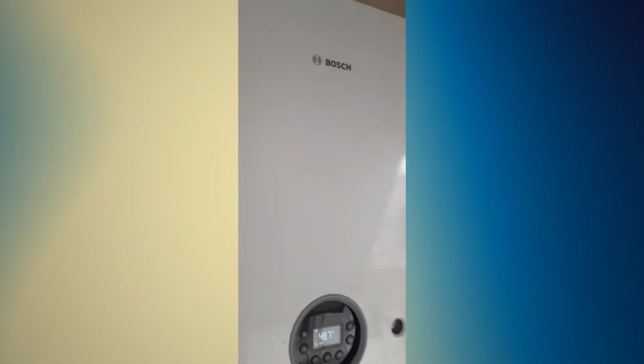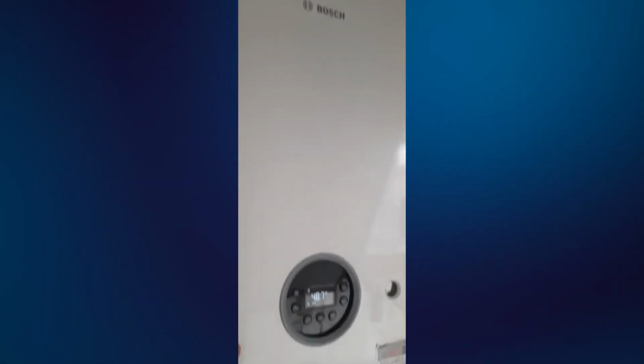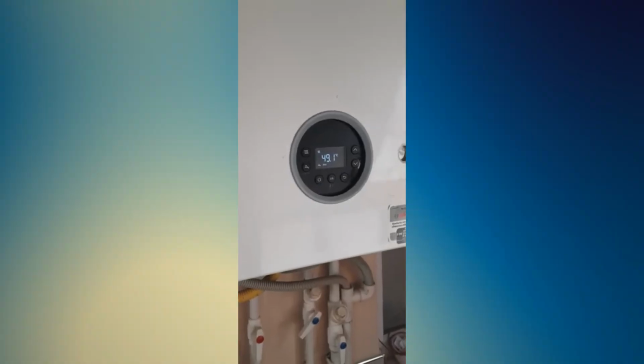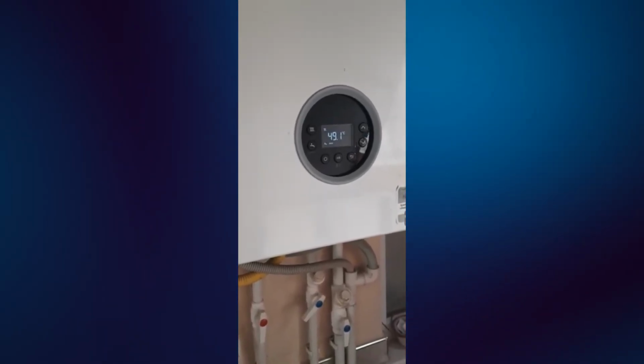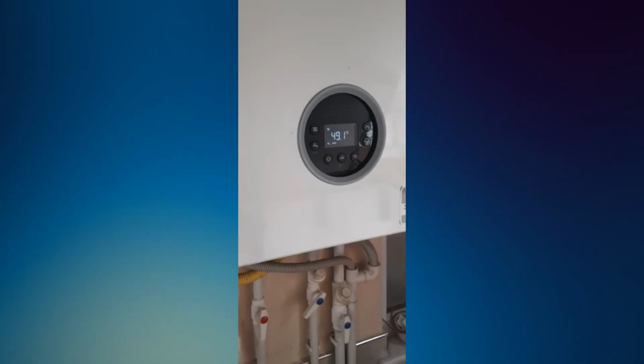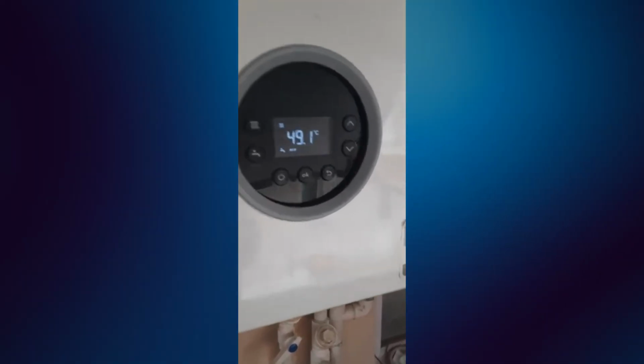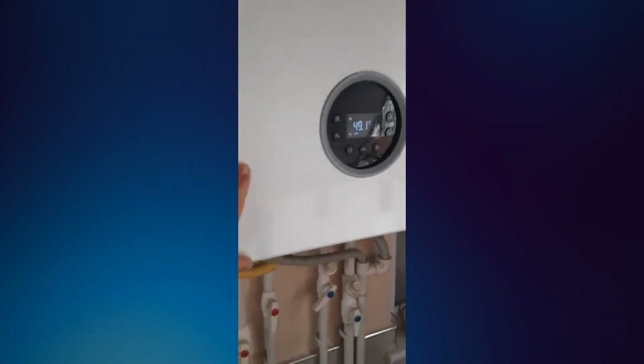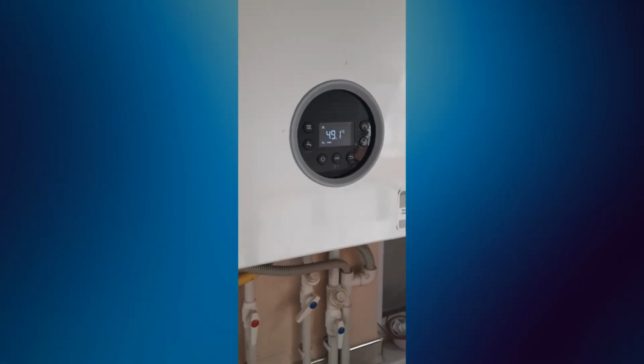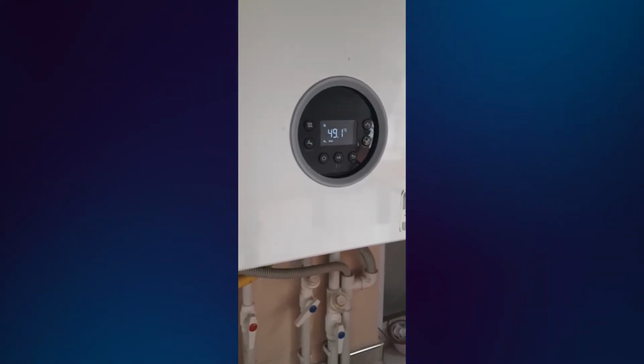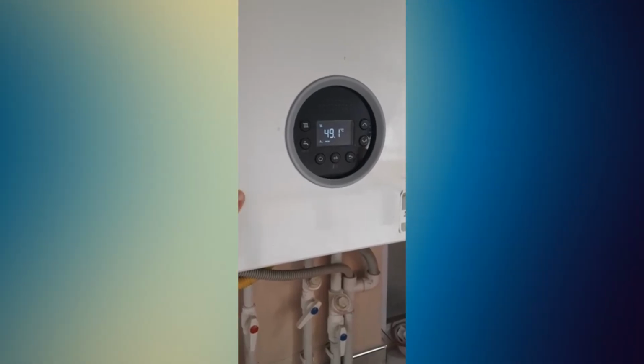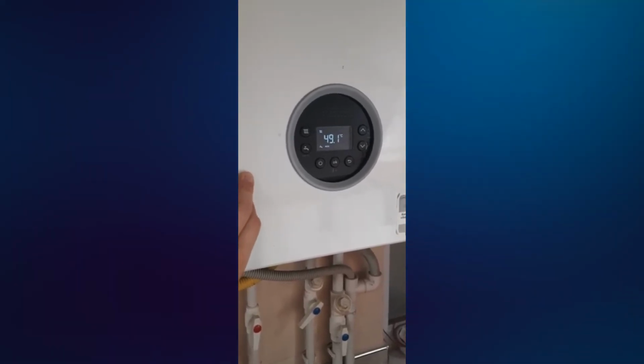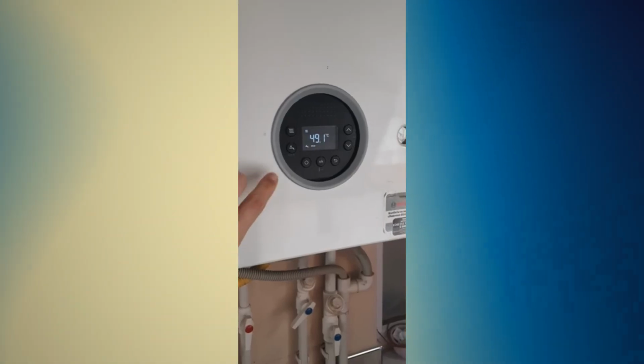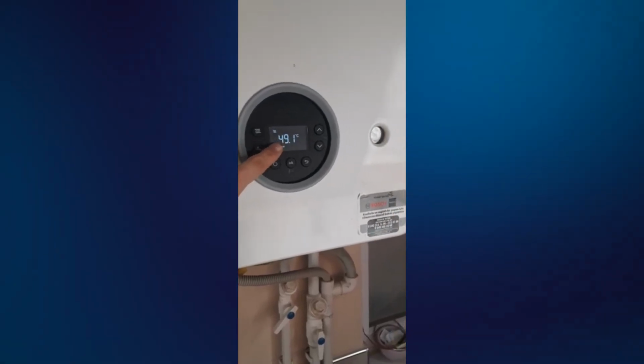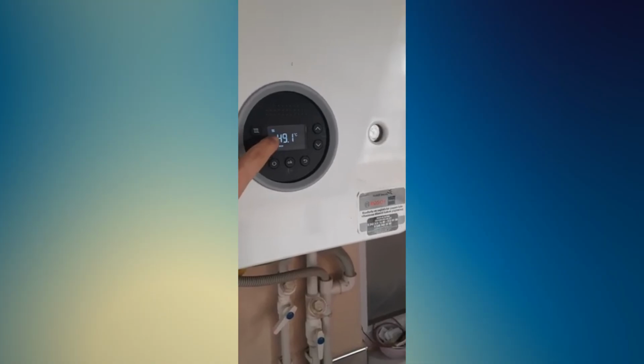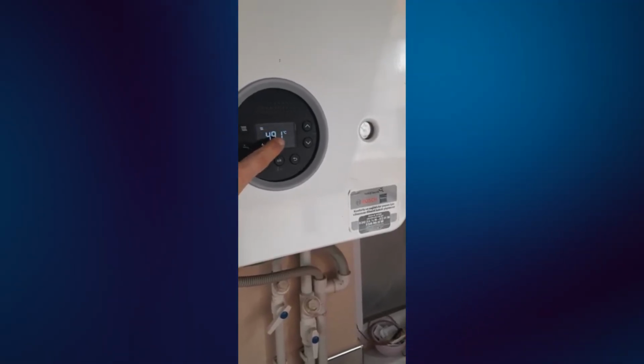If your Bosch, Buderus or Worcester boiler is showing error 2951, the first thing to understand is that this code can depend on the exact model. On many Worcester Bosch and Bosch-family condensing boilers, error 2951 is commonly linked to repeated flame loss. In simple words, the boiler has tried to run, but the flame has been lost too many times, so the appliance locks out for safety.